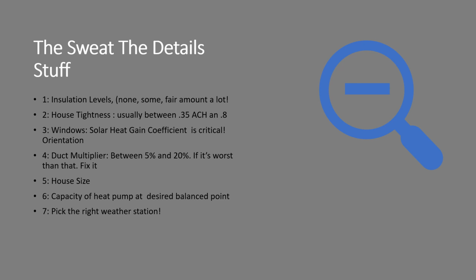Duct multiplier is critical. 15 to 20% is really a pretty good estimate. I know many of you don't do duct leakage tests, and that's perfectly okay, but I urge you to do what I call the Homer Simpson duct leakage test. That's where you turn the system on and let it run for a while, so you're either heating or cooling, and go around to each register. Is there conditioned air coming out of each register? If not, go find out why. It might be a disconnect or it could be a closed damper.